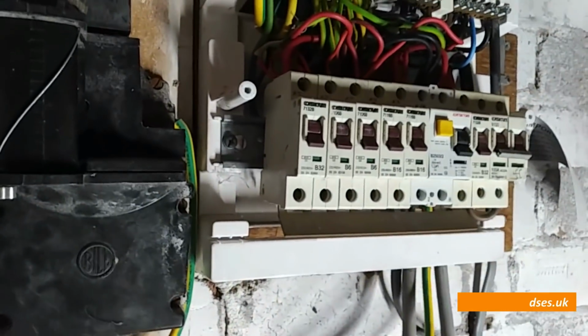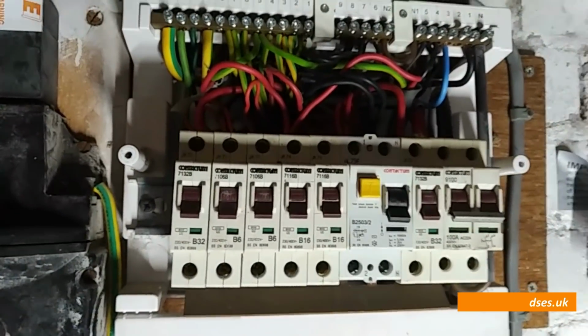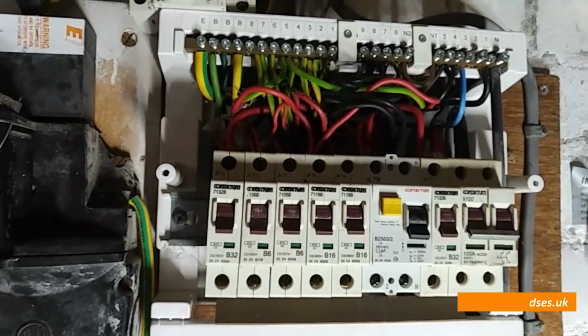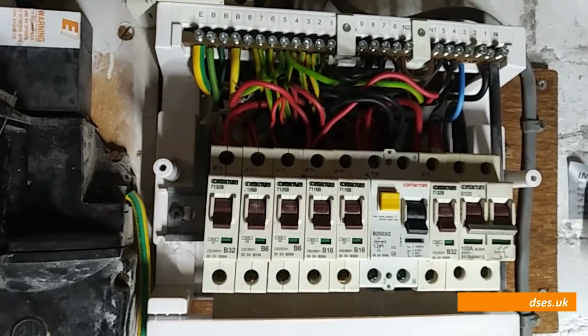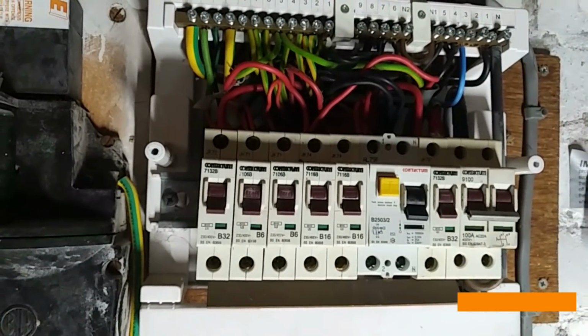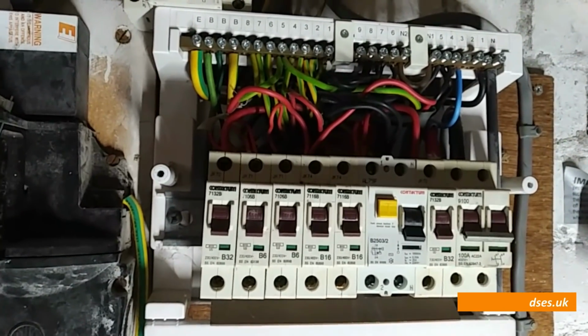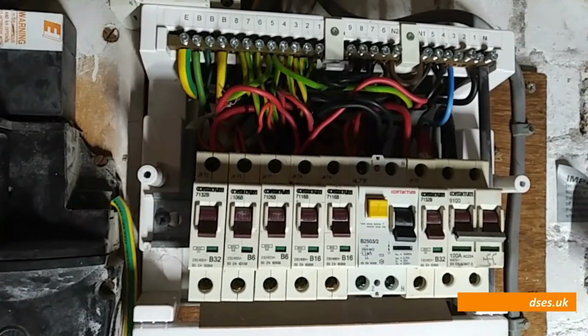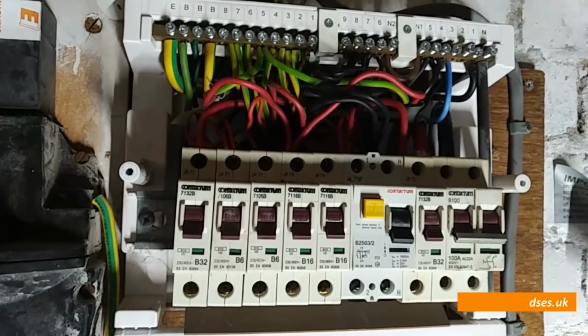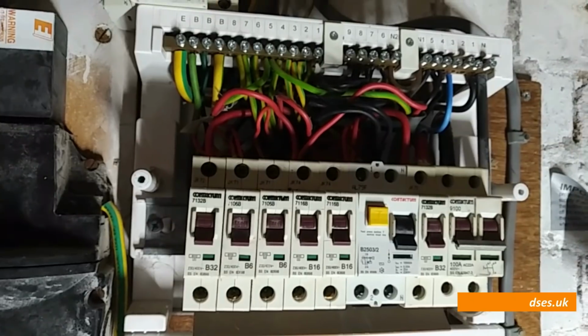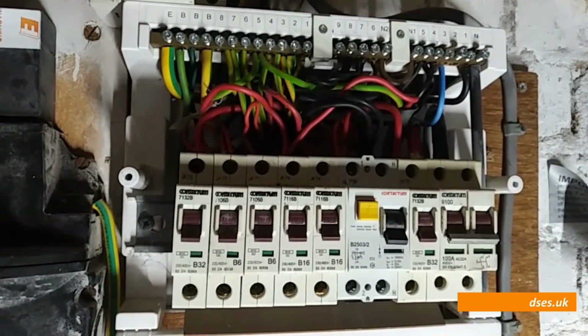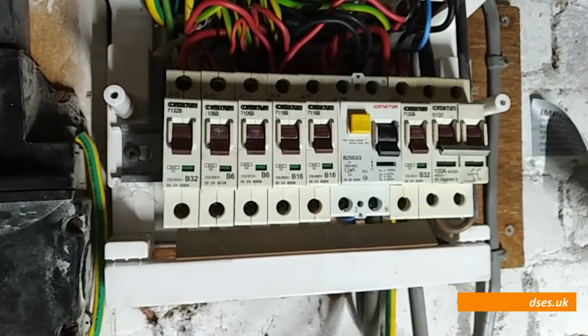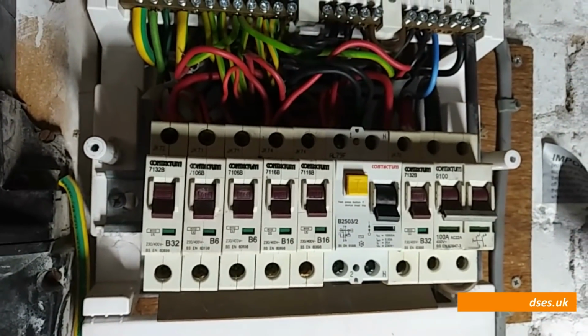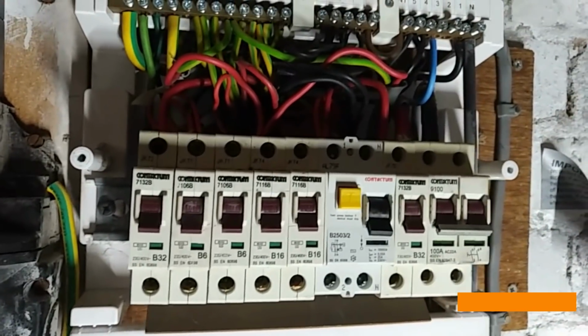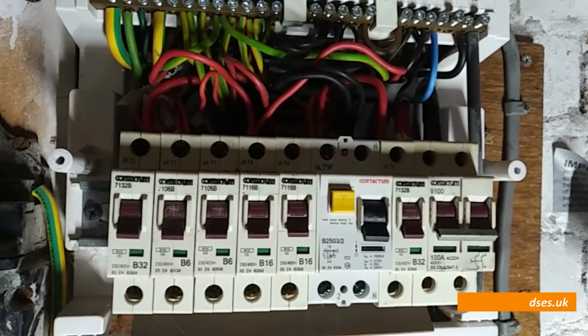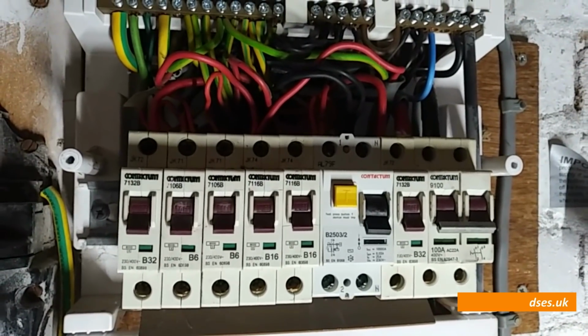I think what's happened in the past is the previous guy's come in, he's recognised that we've got lots of sockets spidering off from the ring - spurs off spurs and that sort of thing - and he's figured, well, okay, 32 amps is probably a bit much for this sort of configuration where we've got 2.5mm cable spidering off to lots of other sockets. So we can't really drop it down to 20 amps because it's serving pretty much the whole house, and 20 amps is just kind of nuisance trip when they have the kettle and the toaster on. So we'll go for a compromise - we'll put in a B-curve 25 amp device with 30 milliamp protection for earth leakage, and that will give them their additional protection as well as their overcurrent protection.